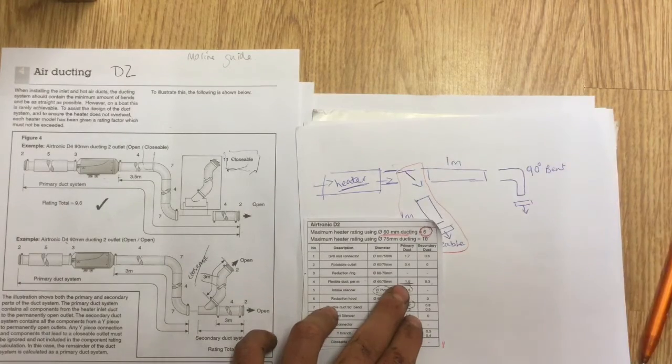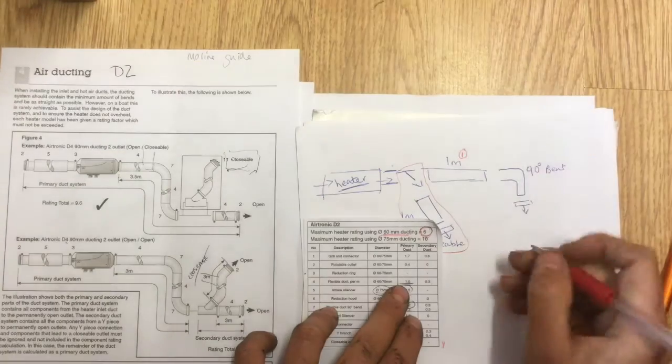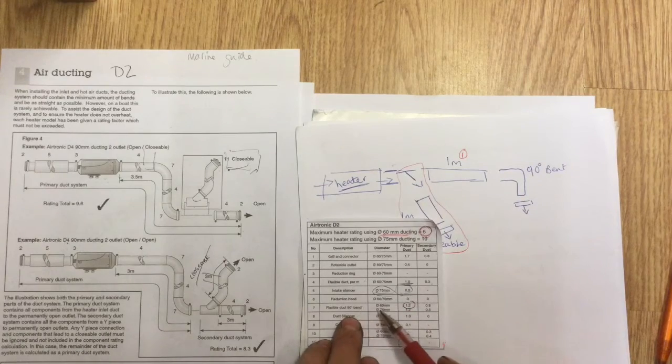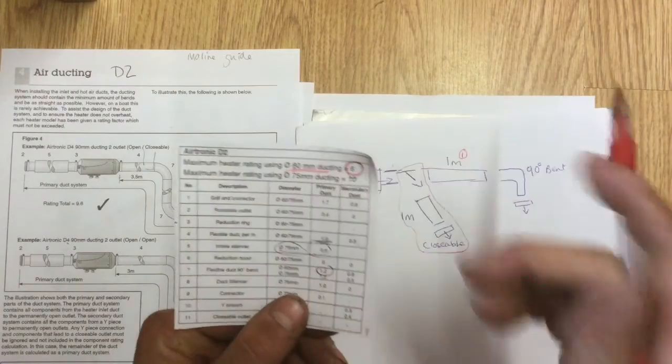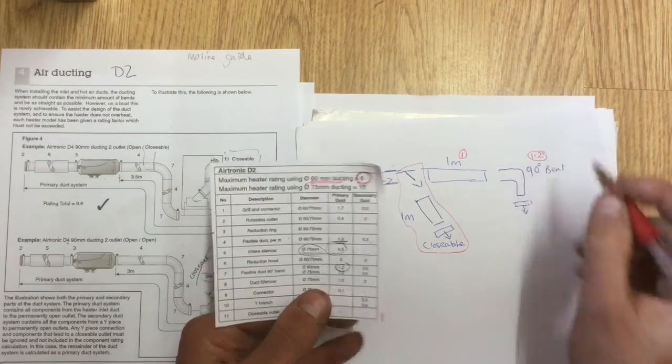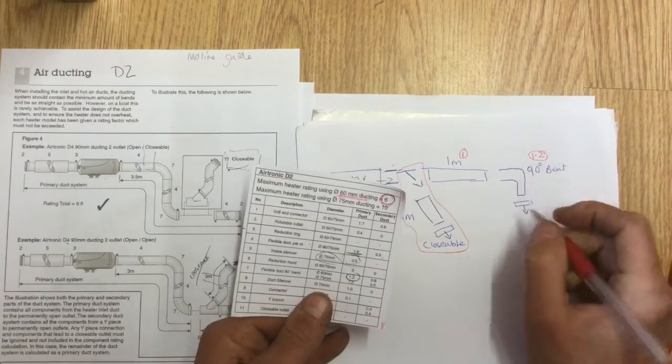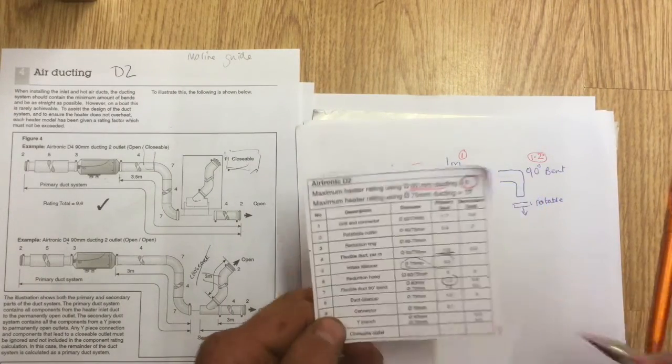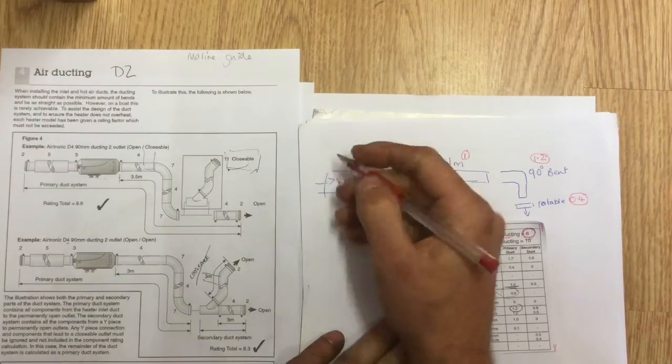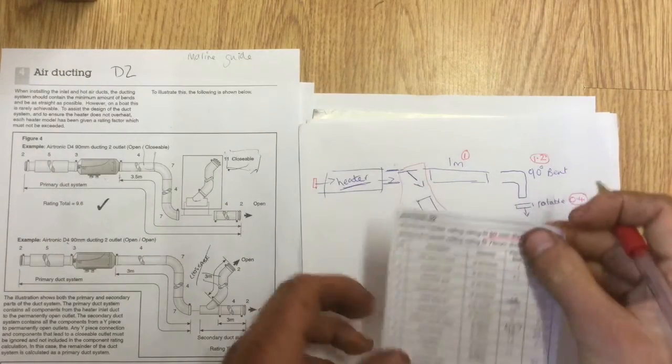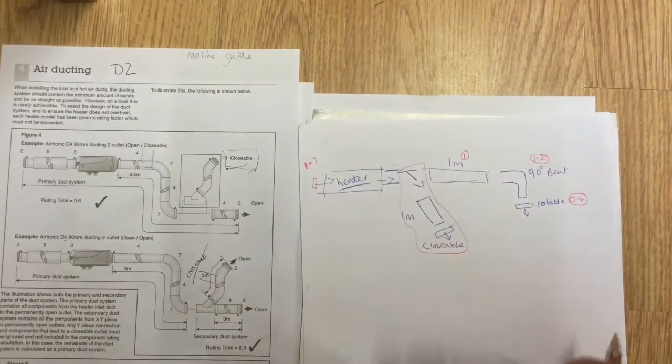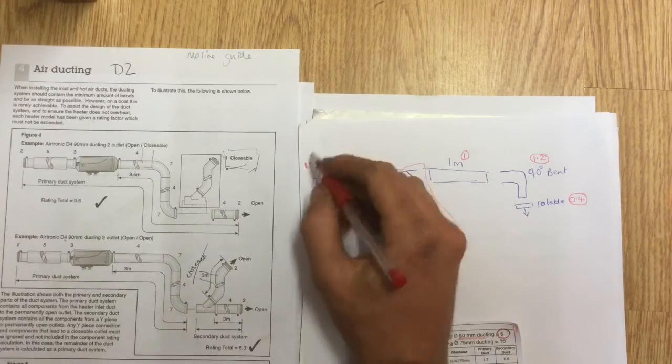Then we've got a 90 degree bend. Looking down this list, we've got flexible duct 90 degree bend at 60, so that gives us 1.2. Then on the end this is a rotatable vent. Looking down here, I've got rotatable outlet that's worth 0.4. On my intake I need to consider - you might have an intake grill just to stop things going in there, and that's worth 1.7.